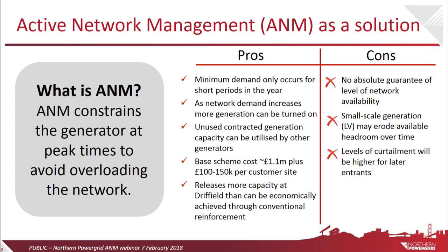It's effectively a monitoring and control scheme that interfaces with both the distribution network, our network, and generators in this instance to constrain generator export at critical times to avoid overloading the Northern Power Grid network. The ANM scheme is effectively a substitute for the traditional expensive reinforcement that would otherwise be necessary. This scheme comes in at around £1.1 million plus about £100 to 150k per customer site. So you can see that it's considerably cheaper than the alternative, more traditional connection methods that we have at our disposal that would involve reinforcement or connection outside of the group.